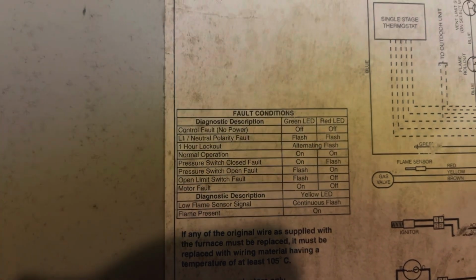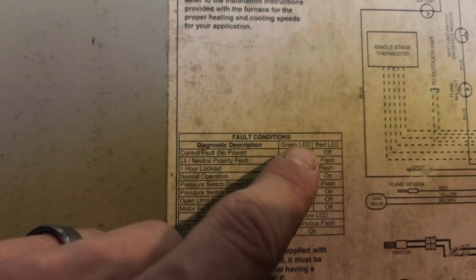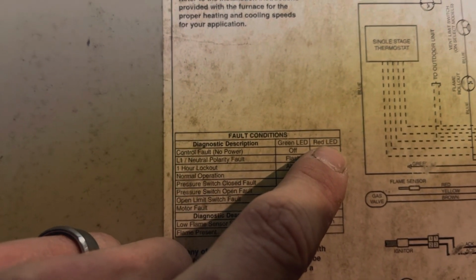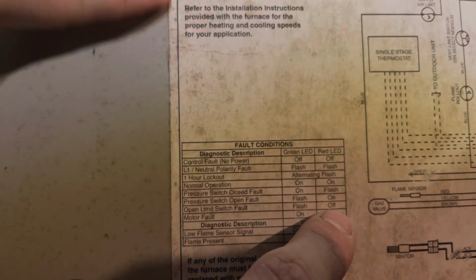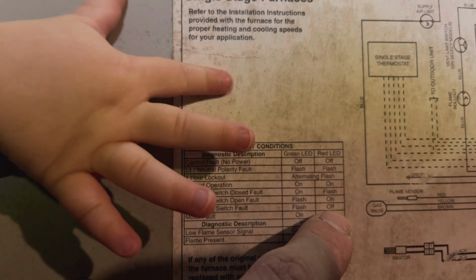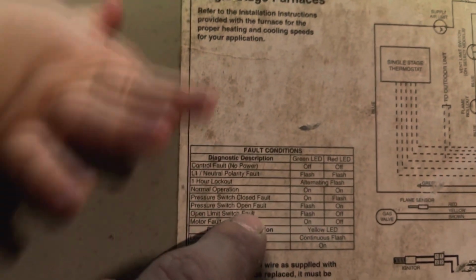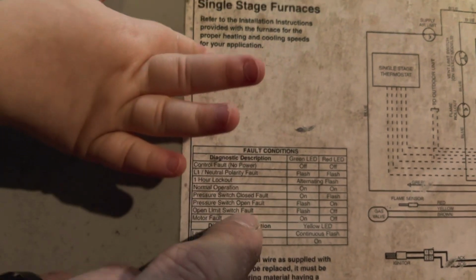Now, if you zoom into the fault conditions, you can see your green LED, red LED. So you want to scroll down. We had our green LED flash, and our red LED was off. So that was our fault condition, which was an open limit switch fault, which can mean many things, many problems.